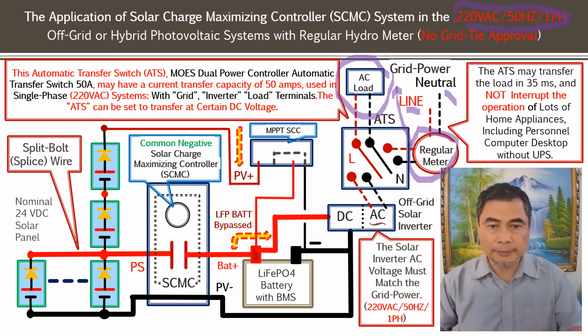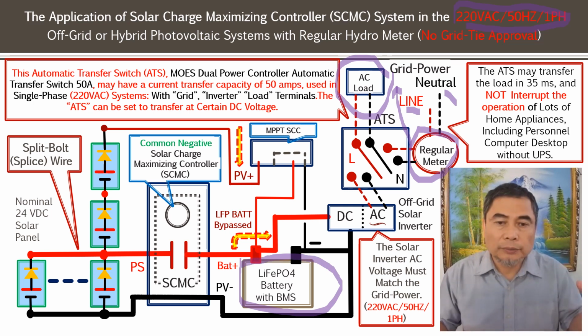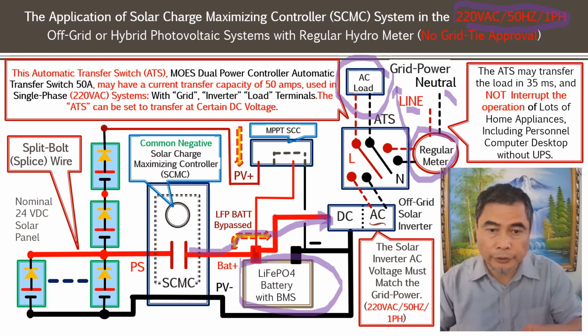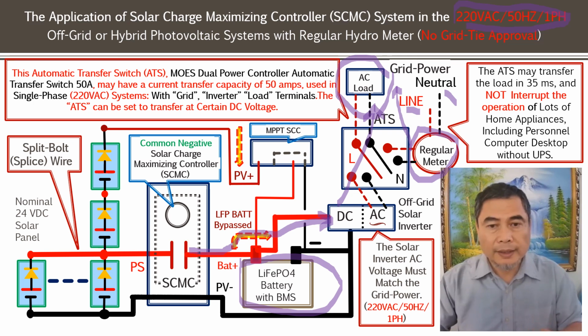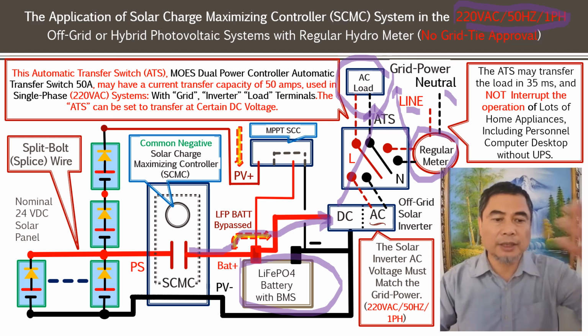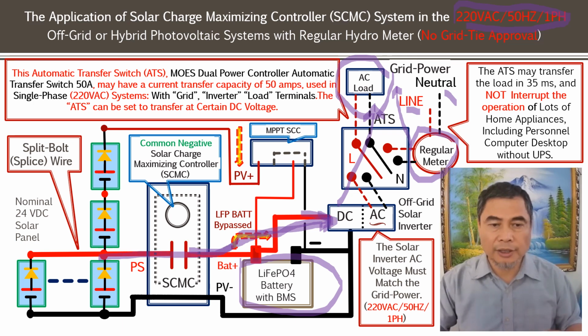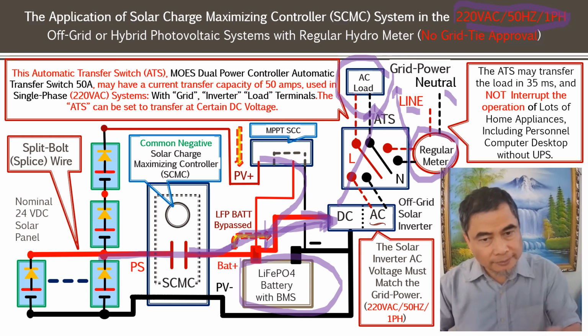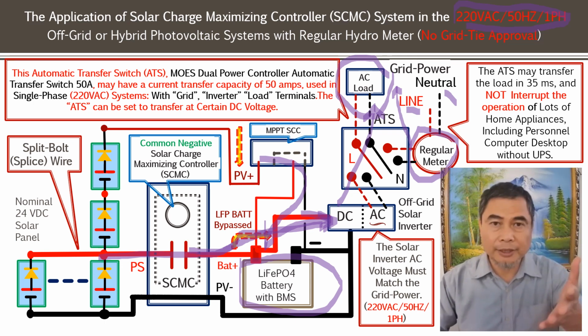It will be very good to set up this system, because the solar charge maximizing controller, of course this is a common negative system, means this battery bank will not need to be huge, because the majority of the current will go directly to power the DC load, which is the inverter, the off-grid solar inverter in this case, to power that AC load directly without charging the battery. So when the sun comes out and we get 120 amps coming into this line, we may get 80 amps coming into the MPPT solar charge controller. You can have maximum 200 amps capacity, times a 24 system, or times a 48 system. That's quite a lot of power, a 5 kilowatt or 10 kilowatt power system.